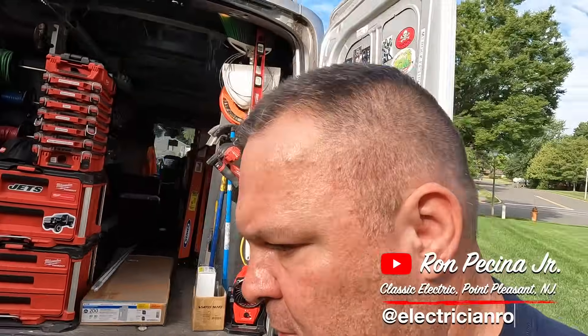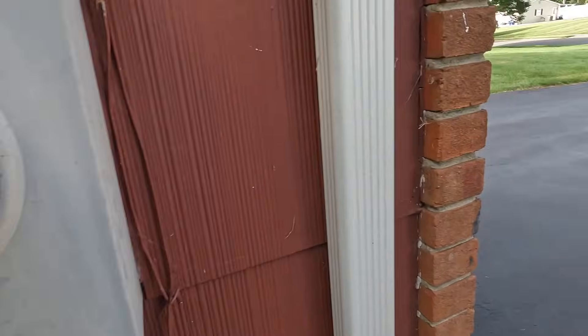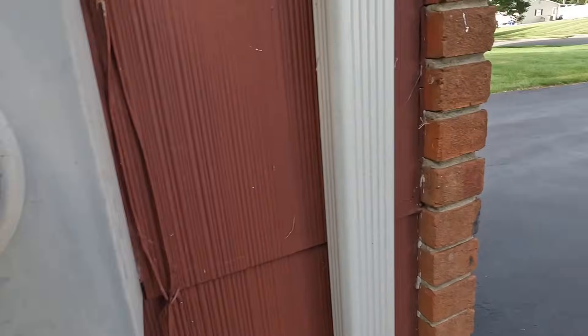Hey guys, welcome back to the channel. This morning I'm in Freehold, New Jersey and we're going to be upgrading — well, actually just a panel change — because we have an underground service, 200 amps right here. I haven't opened this up yet. Fortunately it's not locked, that's good. We got a permit — permit took about eight or nine days to get approved. It's approved, and this is the old Pushmatic panel we're going to be changing.